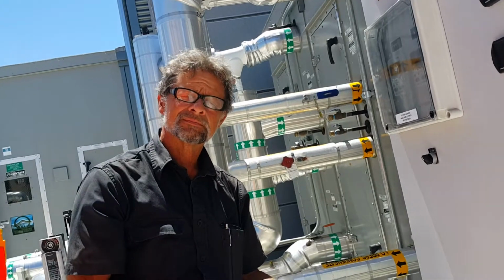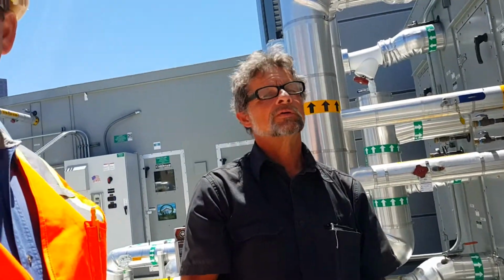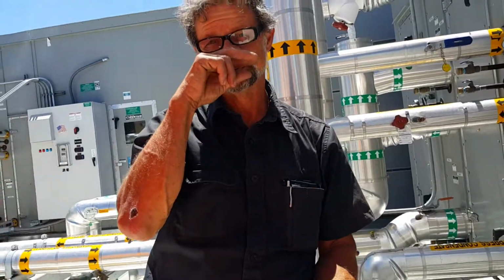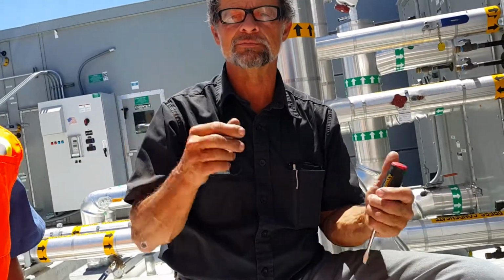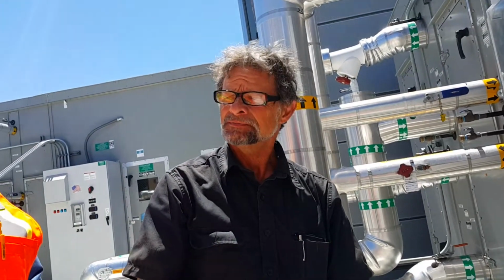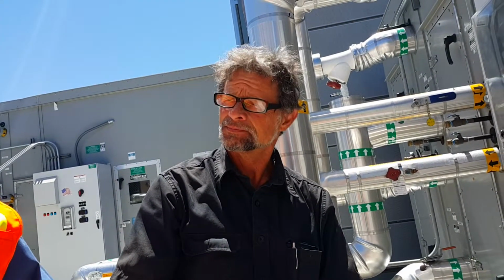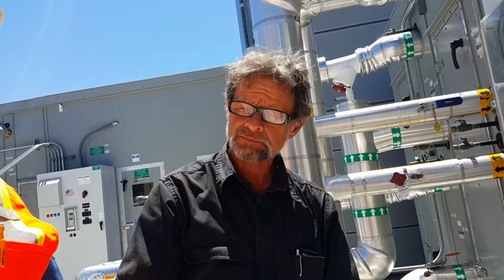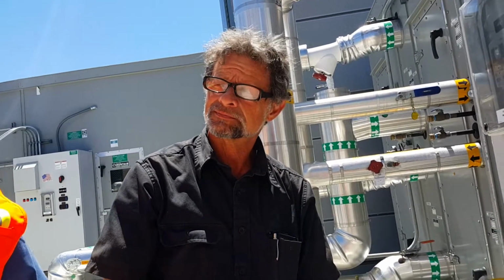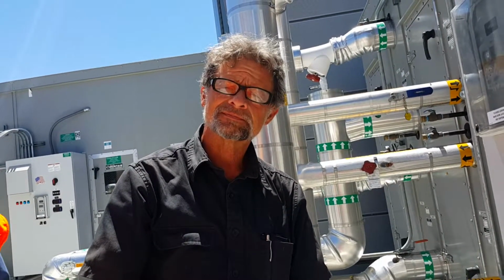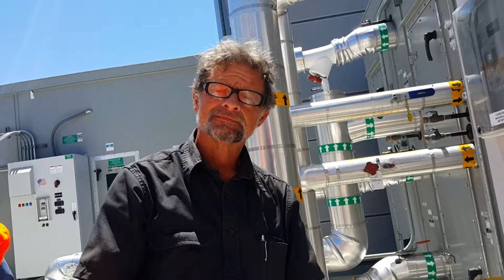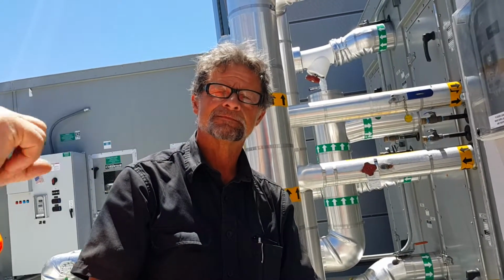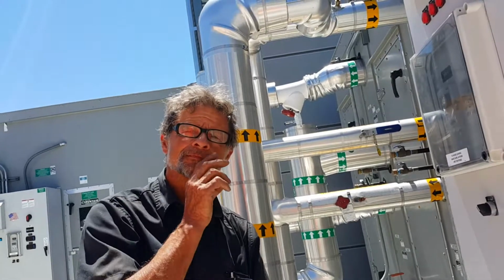Yes. So they can essentially be put in the same one, though. Not every one is programmed the same. This one has 4 motors, that one is 6. Okay. Different amp ratings. Okay. Basically, it's working like a keypad though. If you want to turn a unit off and the head's broken on that one, let's say, you could take this head, bring it over there, turn it on, and it'll run on the internal VFD drives information, not the head information. Right. As long as you don't download the information into the drive, the parameters. Okay. Got it.